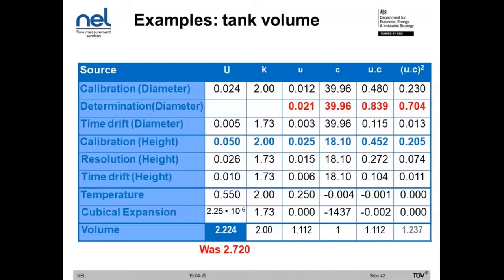So what we've seen with this process is that the diameter measurement has been performed using straps. So you're measuring the outside diameter of the tank and determining the diameter that way. So if we say to the measurement engineer, well, instead of taking 5 measurements of the tank, we want you to take 100 measurements, and then we'll get a more robust statistical analysis. If we do that, again, we can reduce the uncertainties of this component.